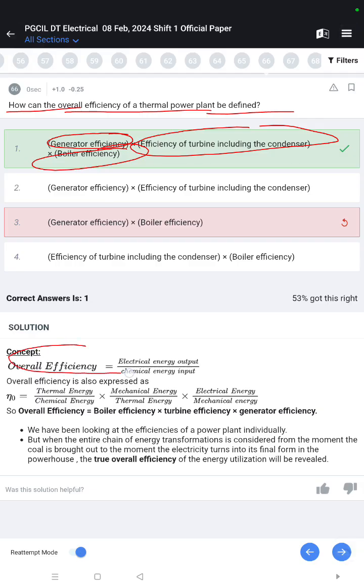How can the overall efficiency of a thermal power plant be defined? Generator efficiency × efficiency of turbine including the condenser × boiler efficiency. Overall efficiency = electrical energy output / chemical energy input. Overall efficiency is also expressed as thermal energy / chemical energy × mechanical energy / thermal energy × electrical energy / mechanical energy. Overall efficiency = boiler efficiency (thermal energy / chemical energy), then turbine efficiency (mechanical energy / thermal energy), then generator efficiency (electrical energy / mechanical energy).